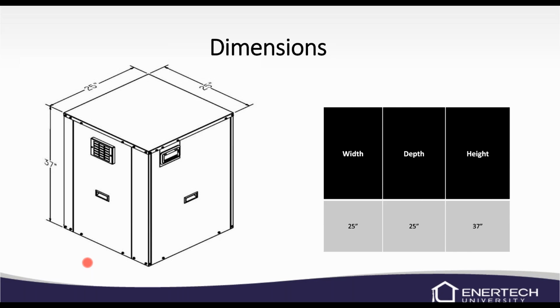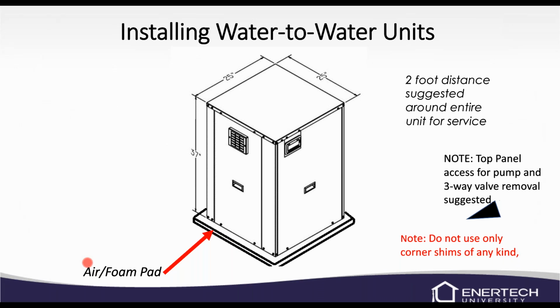Dimensions, again, like I said earlier, the 040 and the 060 are the same size, and they're about 37 inches tall and 25 inches wide and 25 inches deep. Make sure you're setting it on a pad. We say air foam pad here. We've got a newer pad that's a rubber pad. It's about 1 inch thick, and that's what I would recommend.